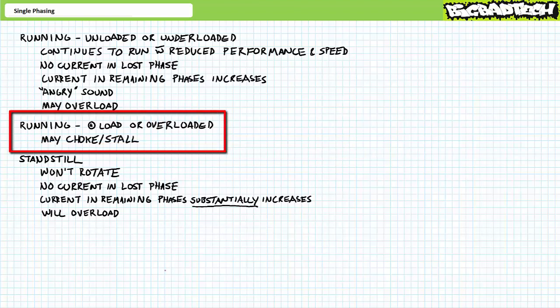The remaining scenario — loaded motors single phased while rotating — can be a mix of both worlds. A motor experiencing at or above rated torque when single phased can be expected to choke, stall, and eventually come to rest, experiencing the same fate as a motor single phased at standstill: tremendous current draw and a quick overload. If, however, the motor was experiencing oppositional torque below rated torque when single phased, we might expect it to continue to run at a reduced speed and increased current in the remaining phases, producing an ugly growling sound. Lacking overload protection, this motor might eventually damage itself over time.